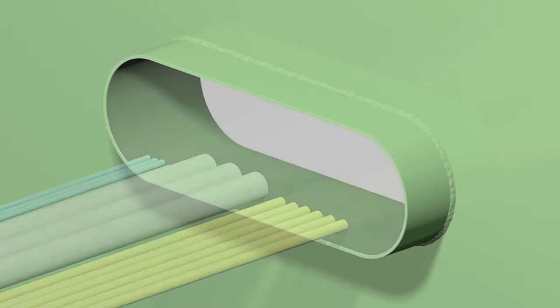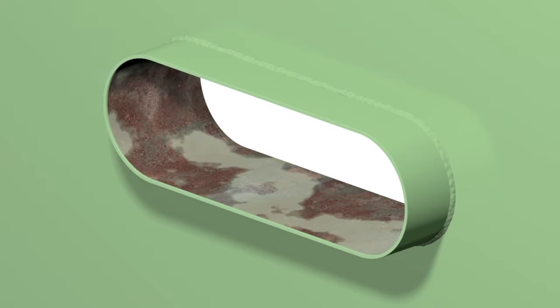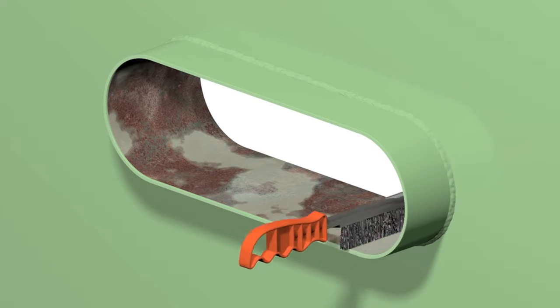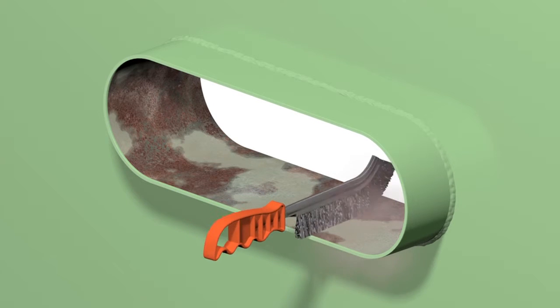The ideal transit frame for a rise penetration is clean and coated on the inside. However, transit frames that are welded into the partition earlier on might look different. In that case, the inside of the frame has to be cleaned thoroughly. With a steel brush or by blasting, the corroded inner surface of the transit should be treated to remove corrosion. The excellent adhesive properties of the sealing system will be diminished by corroded surfaces.